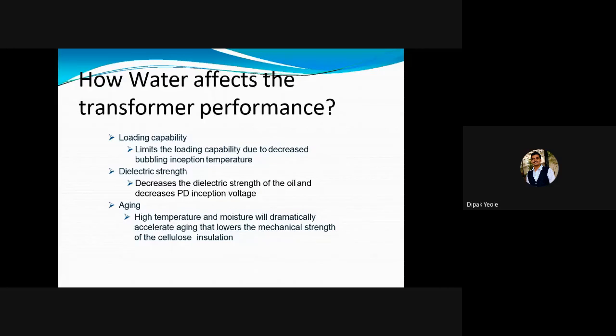We know that the dielectric strength will get affected. Aging can be possible, and loading capability will be affected. It limits the loading capability due to decreased bubbling inception temperature. Dielectric strength decreases, which decreases PD inception voltage. High temperature and moisture will dramatically accelerate aging that lowers the mechanical strength of the cellulose insulation. So in these three conditions, water affects the transformer performance.